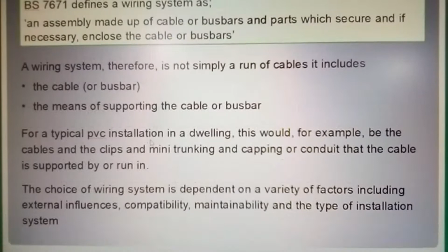Good. Now, BS 7671 defines a wiring system as an assembly made up of cable or busbars and parts which secure and, if necessary, enclose the cable or busbars. A wiring system is therefore not simply a run of cables. It includes the cable or busbar and the means of supporting it. For a typical PVC installation in a dwelling, this would, for example, be the cables, the clips, mini trunking and capping, or conduit that the cable is supported by or run in. The choice of wiring system depends on a variety of factors, including external influences, compatibility, maintainability, and the type of installation system.